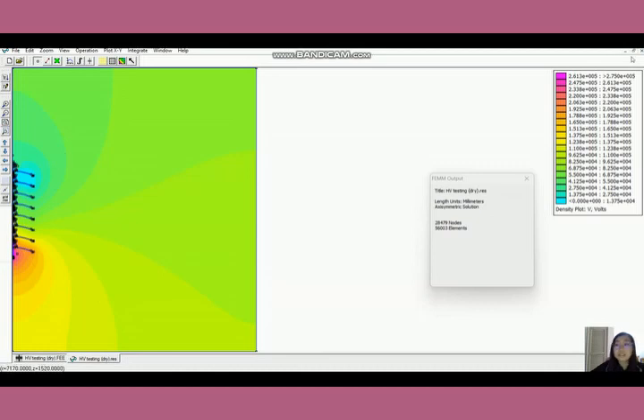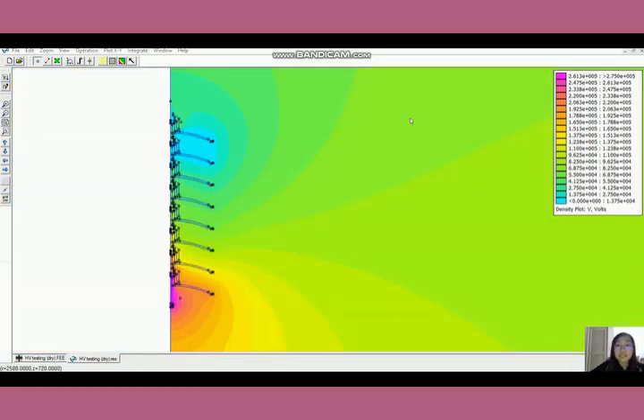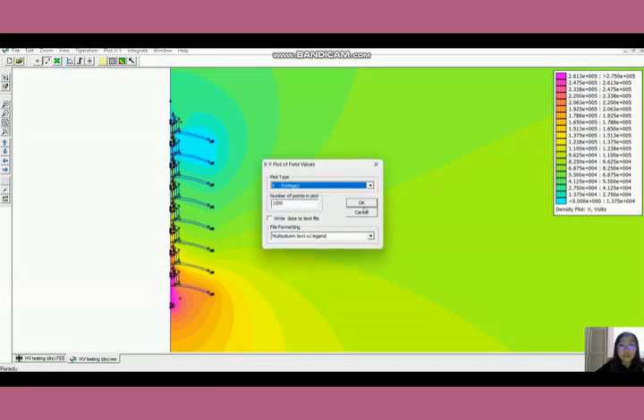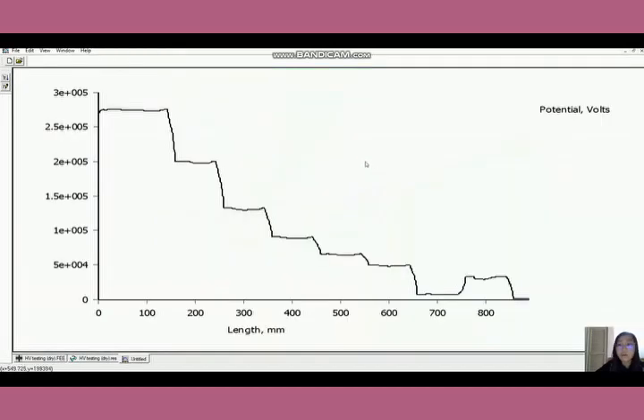From this voltage density plot, we can see that the color fades from dark red to light blue-red according to the insulator shape. After that, we can observe the voltage line graph via the XY plot. According to the voltage line graph, the voltage gradually decreases from 275 kV at the first unit of the insulator until the 7th unit, which is about 13 kV, and it gradually increases at the 8th unit of the insulator.